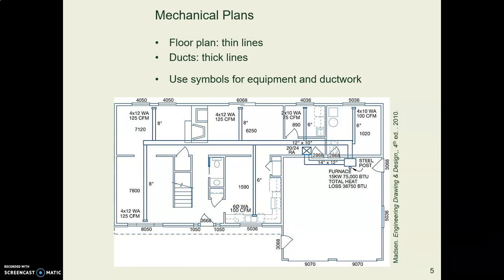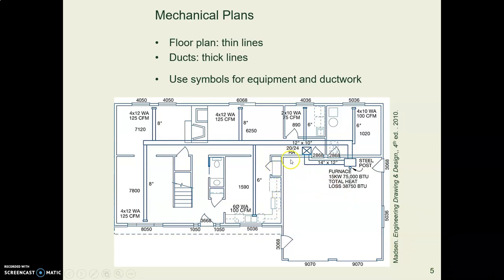If you're doing a separate plan for your mechanical system, you want to communicate to the contractor information about this mechanical plan. They don't need to know all about the walls — you already built the walls. You're trying to tell them about the ductwork, registers, plenum, and all that. So in order to communicate clearly in a separate mechanical plan, you'll make the wall lines thin and the ductwork lines thick. In this example, he has made the walls thin and the ductwork thick, so they do pop out a little bit better.